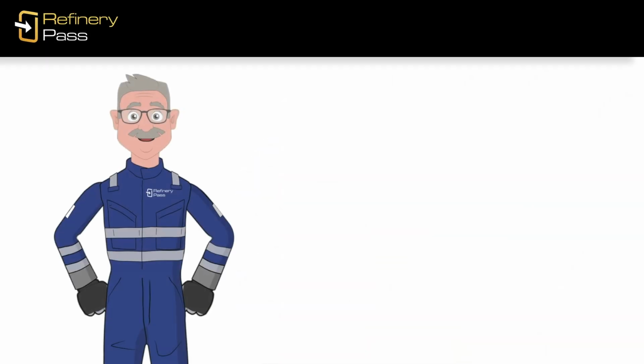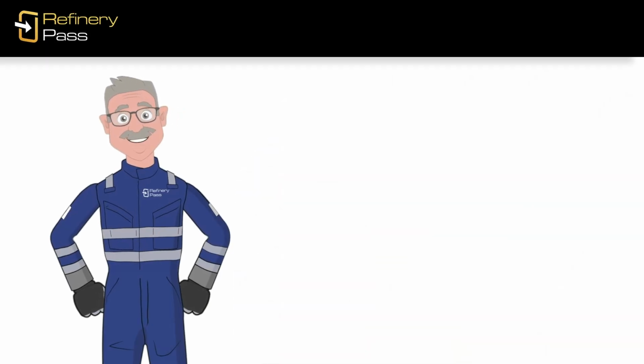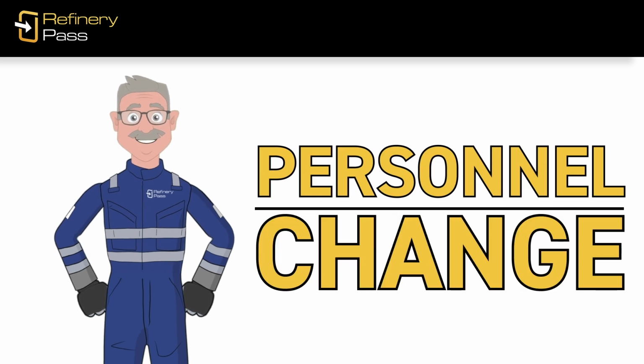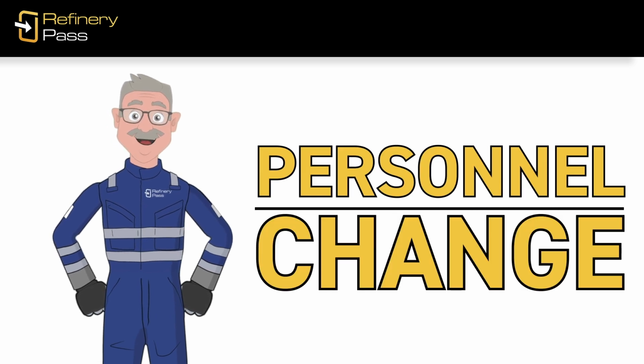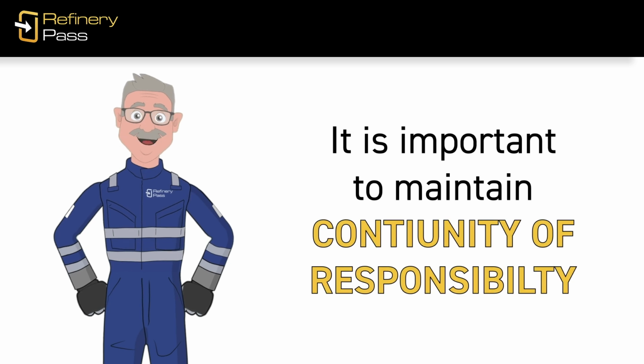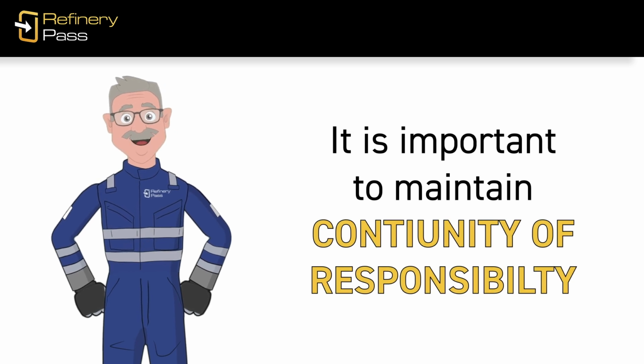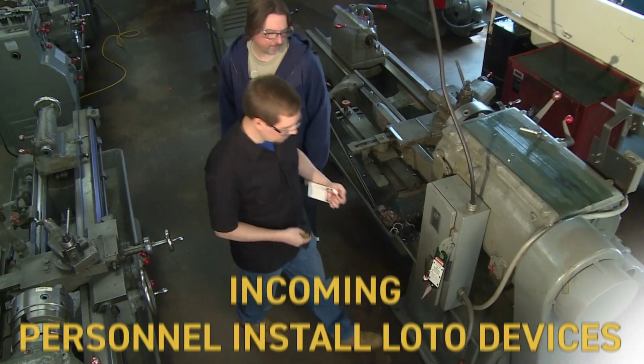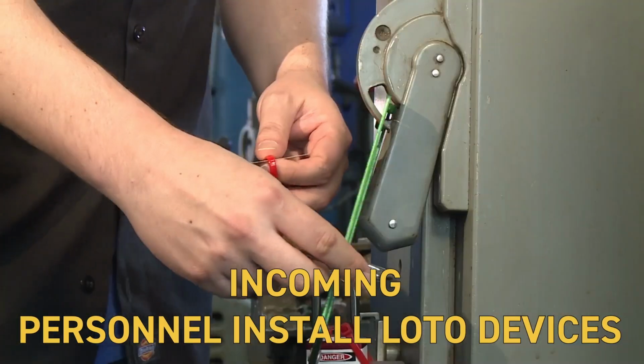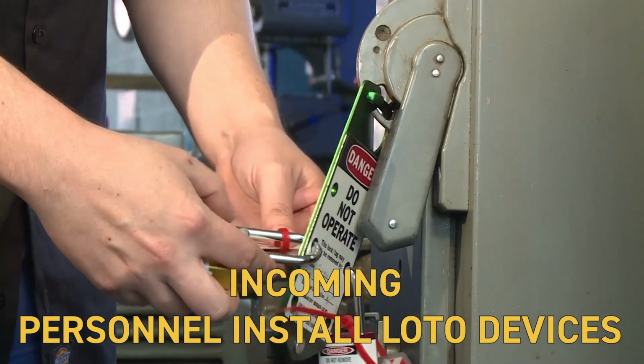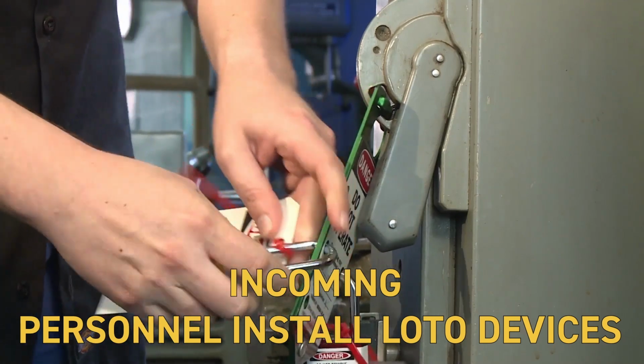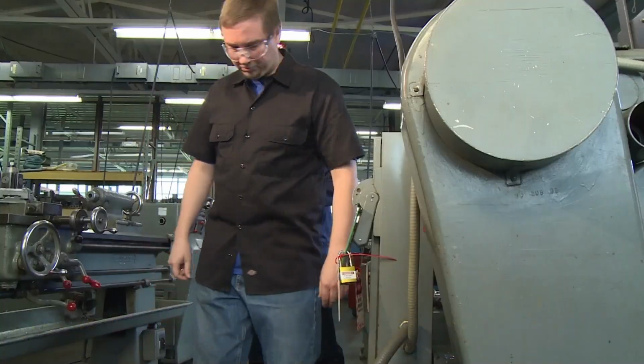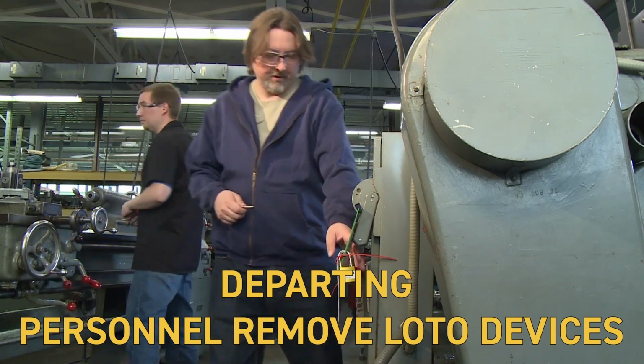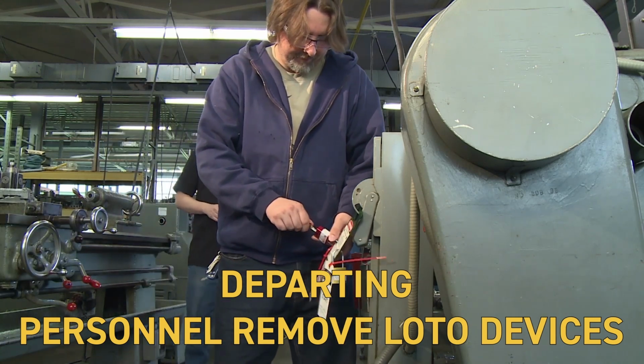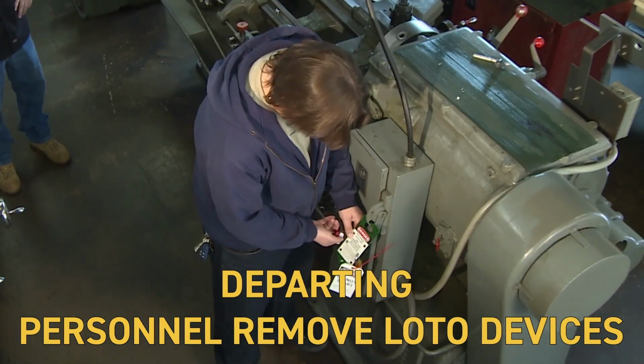The most important procedures of these occurs if you have a personnel change during the time the equipment's being serviced. In these situations, it's important to maintain continuity of responsibility. First, personnel from the new incoming work shift must install their own lockout-tagout devices. Then, the locks and tags that were installed by the departing work shift should be removed.